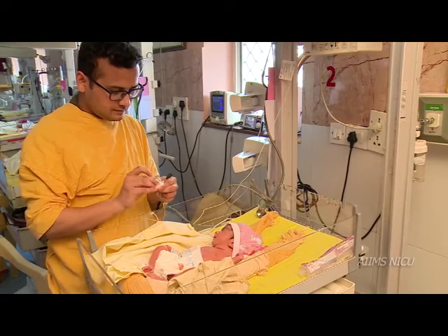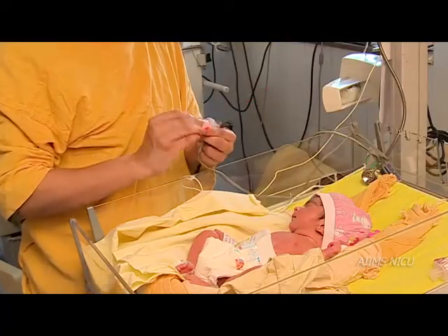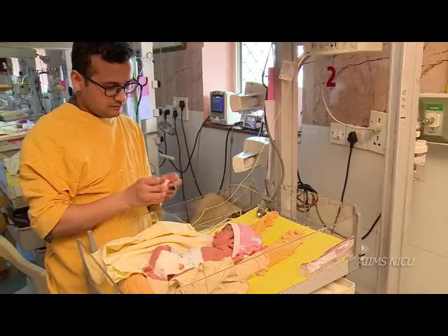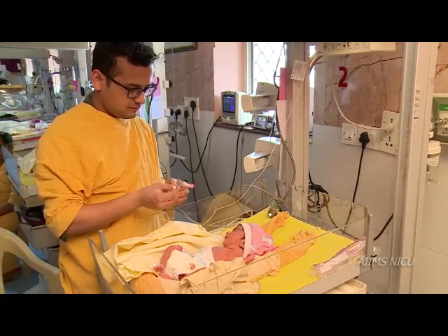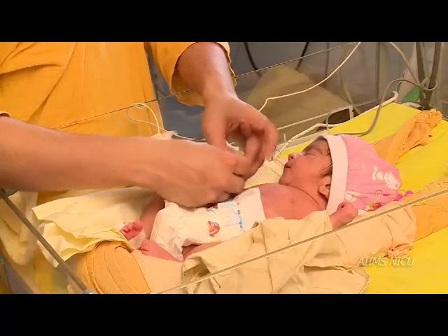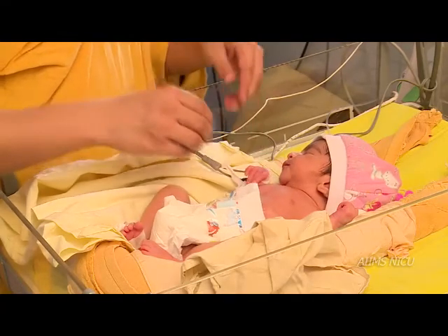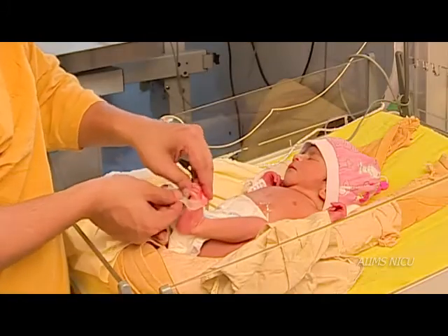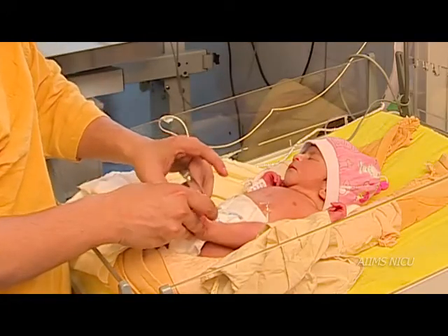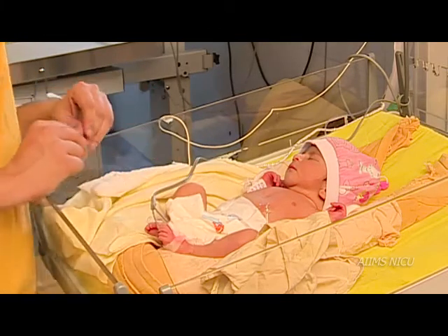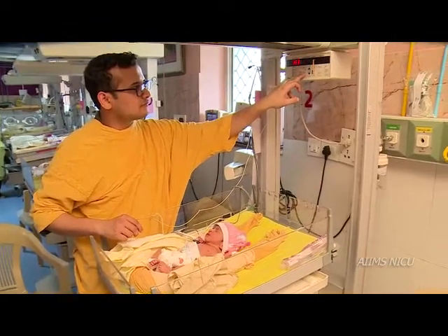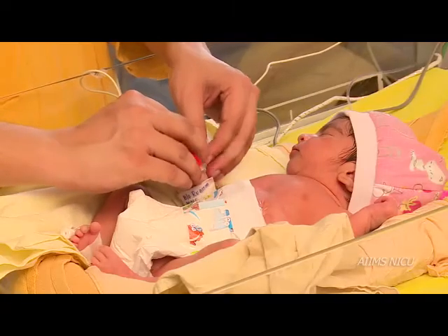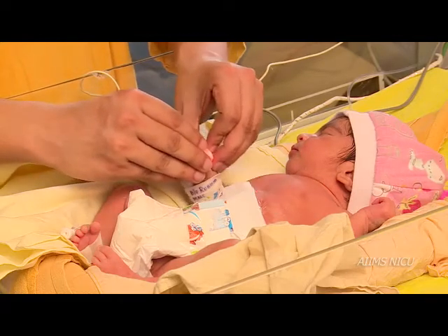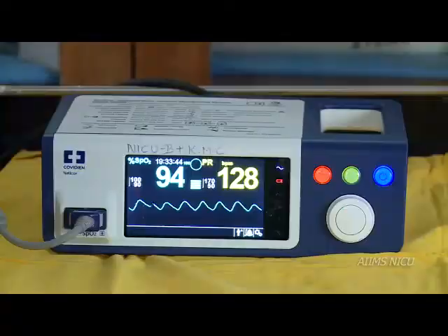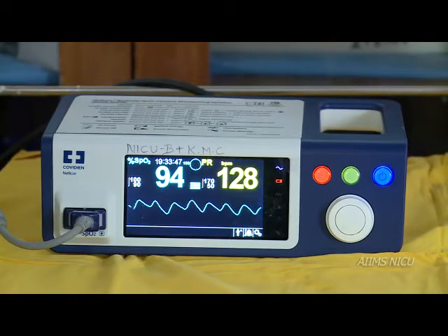Before connecting the oxygen saturation probe, one should clean the SpO2 probe with alcohol-based antiseptic solution before applying on the baby. Clean both the inner and the outer surfaces. The SpO2 probe should be applied to the baby's hand, wrist or foot with light-emitting diode on one side and the photodetector on the opposite side for a good quality signal. Connect the machine end of the probe to the respective slot. Make sure that it is connected firmly and the red light is blinking in the probe before application. Make sure that the pleth wave is good, the heart rate tracing is stable before documenting the SpO2.